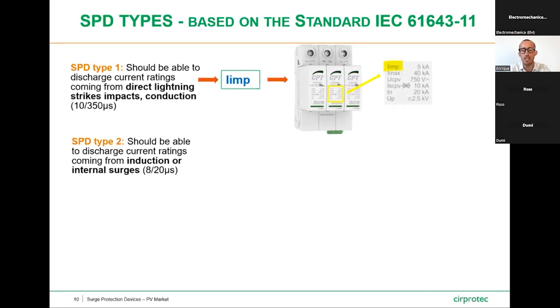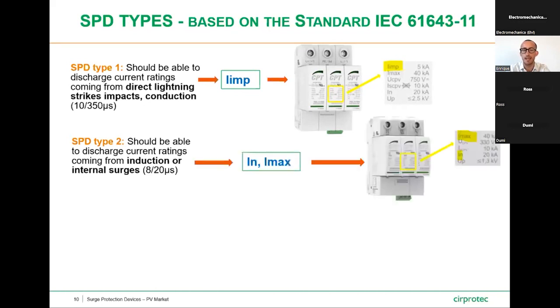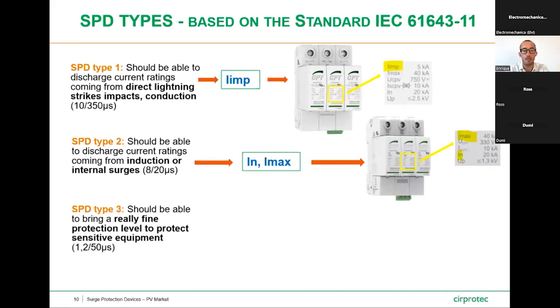Then we have the SPD type 2. Those SPD type 2 should be able to discharge current ratings coming from induction or internal surges. The parameters belonging to the SPDs type 2 are the In and the Imax. And the last type available in the market is the SPD type 3. It's not really typical or applicable for PV installations, but it's important to have it in mind just in case we face a scenario where this SPD type would be required.